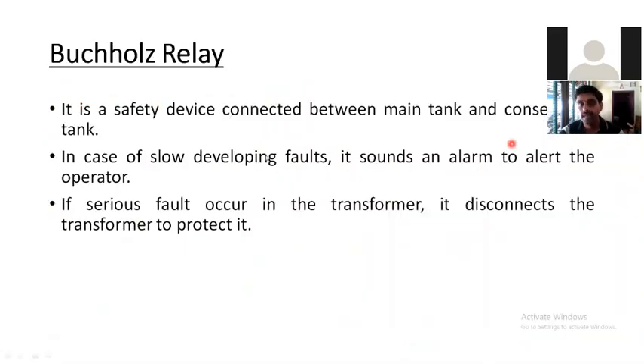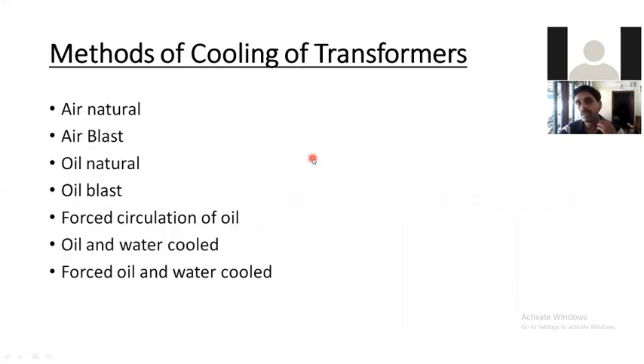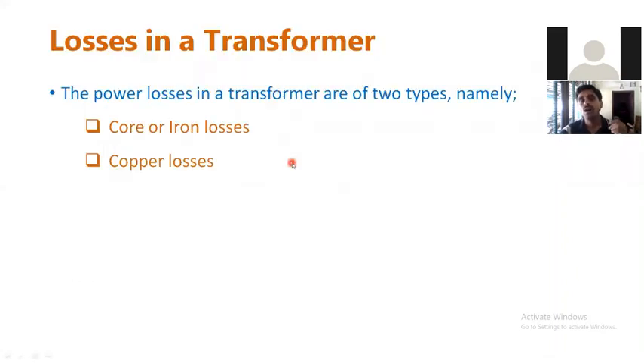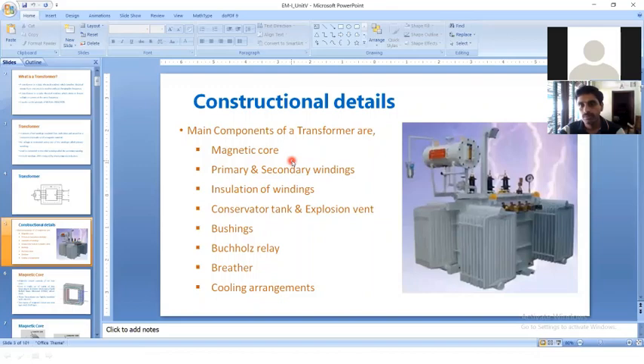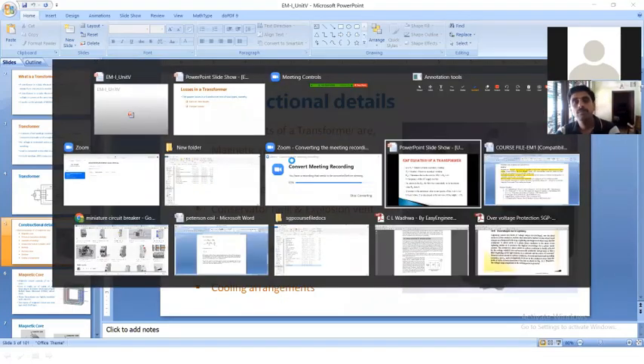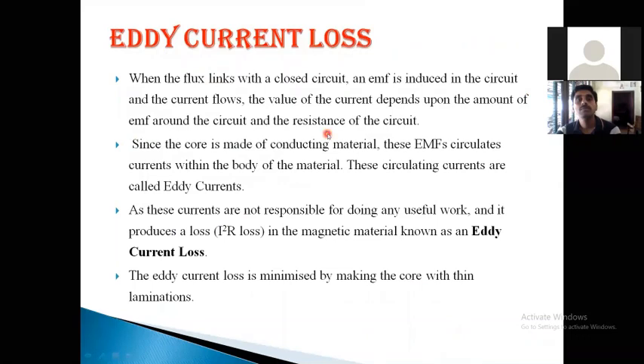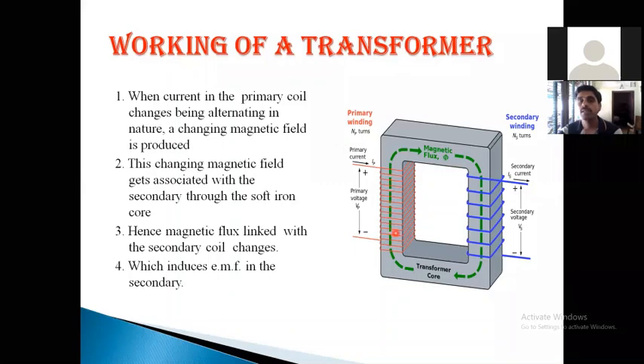Coming to the Buchholz relay, as I said, it is kept in the pipe from the conservator tank, in this direction. If any fault is there, the relay sounds the alarm buzzer. Therefore, we come to know if there are any small internal faults, so that they won't lead to a large fault. For a detailed explanation, you will study this Buchholz relay in the third year. Methods of cooling: air natural, air blast, oil natural, forced circulation of oil, oil and water, forced oil. These are the various methods of cooling. Before going to the losses in the transformer, we'll go to the working of a transformer. I will discuss it, and we'll go to the EMF equation.